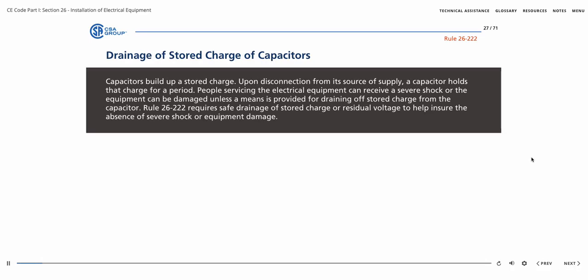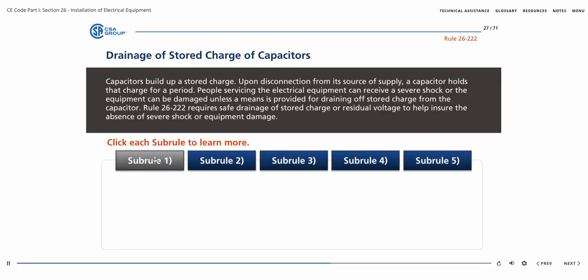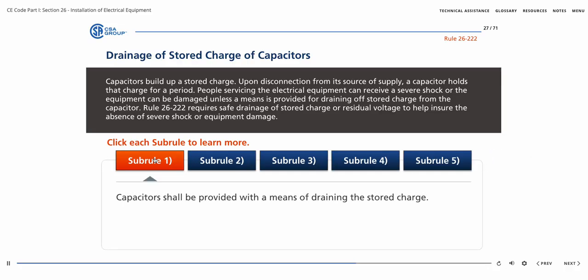When in use, capacitors build up a stored charge. Upon disconnection from its source of supply, a capacitor holds that charge for a period. As a result, people servicing the electrical equipment can receive a severe shock or the equipment can be damaged, unless some means is provided for draining off the stored charge from the capacitor. Rule 26-222 requires there be a means of draining the stored charge or residual voltage left when the capacitor is de-energized.